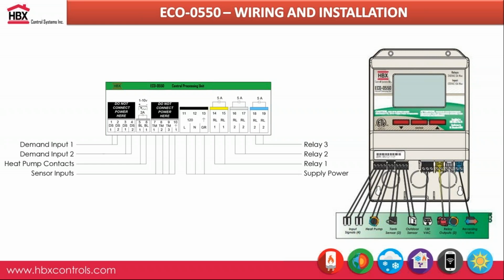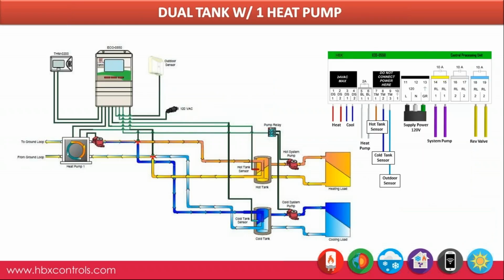sensor. Again, your last 3 relays are for your additional second or third stage heat pump, or if you want us to control your main system pump. And your last relay, pins 18 and 19, is always going to operate the reversing valve, to switch over from heating to cooling and vice versa. In terms of amperage, it's 240, but only 5 amps with the Eco 550, which is still enough amperage for most pumps and heat pumps on the market.